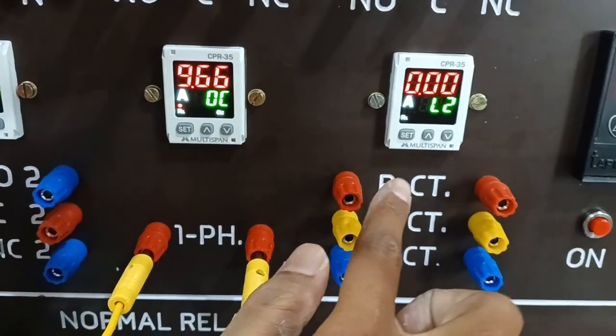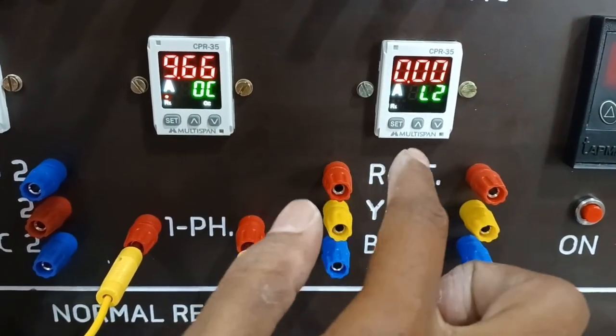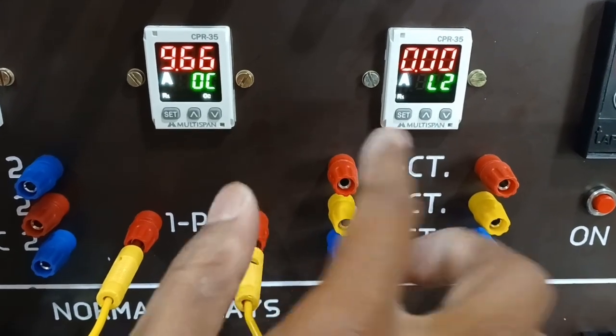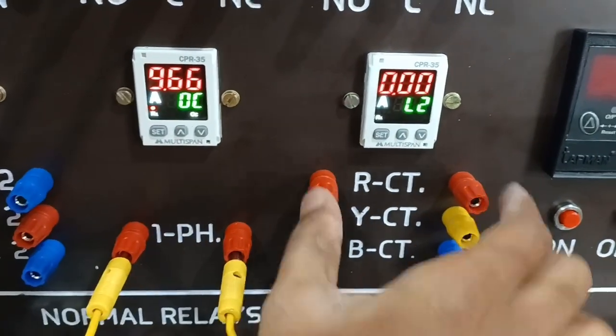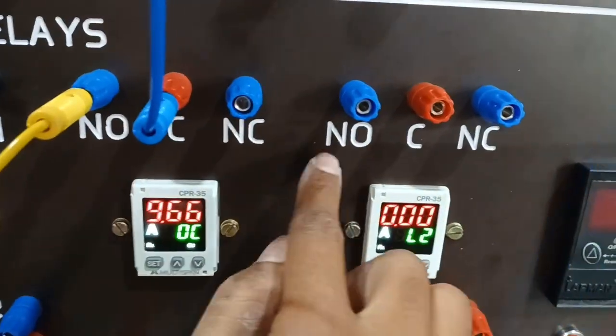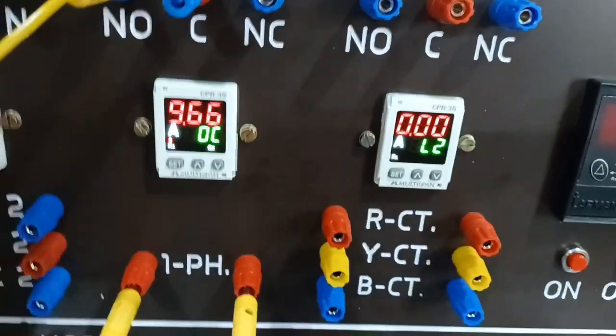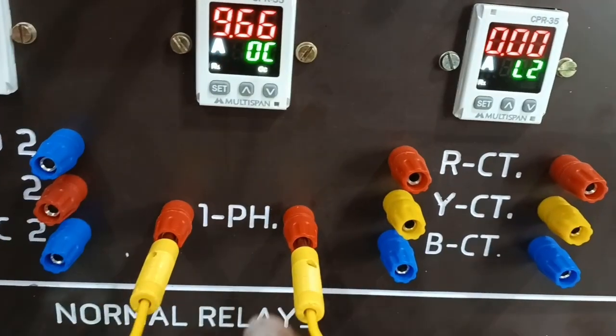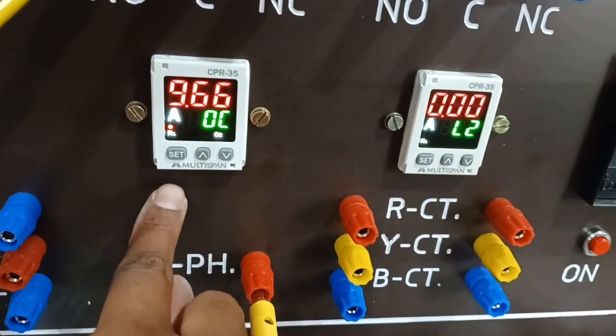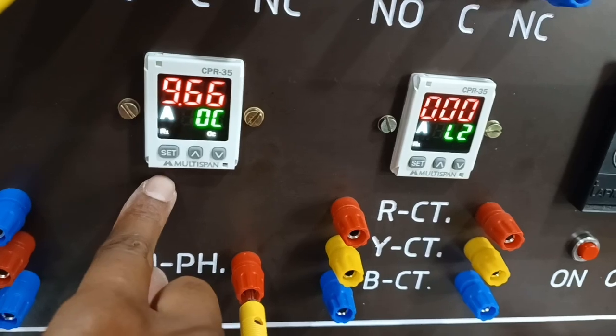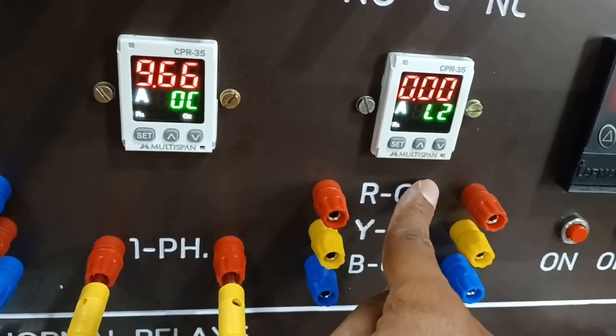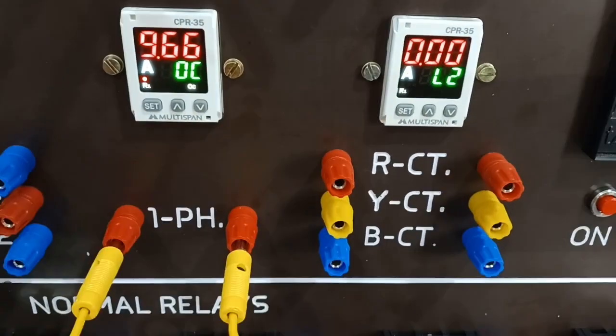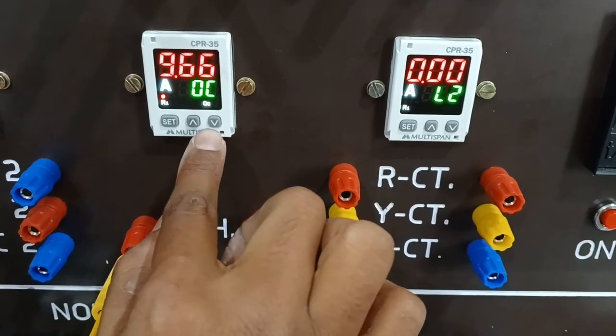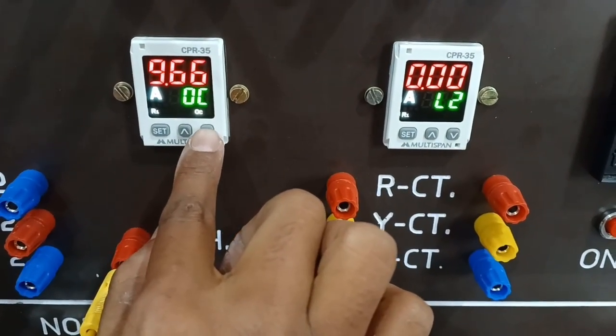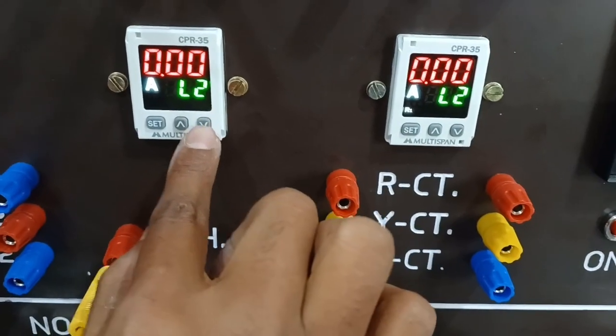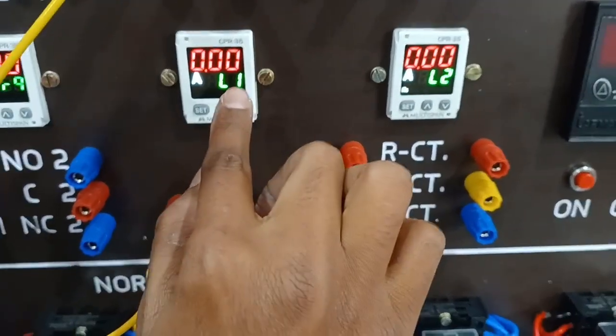Similarly, this relay also works on the same overcurrent function. These are the relay inputs. These terminals are relay contacts, outputs. The difference is this is a single phase overcurrent relay, and this is a 3-phase overcurrent relay. Whenever the relay gets tripped, you need to press this down key for resetting the relay. Whenever you press this down key, the relay will be automatically reset.